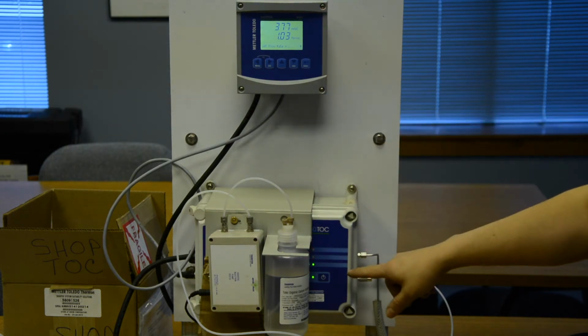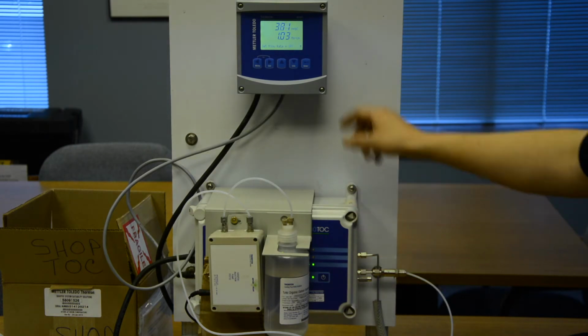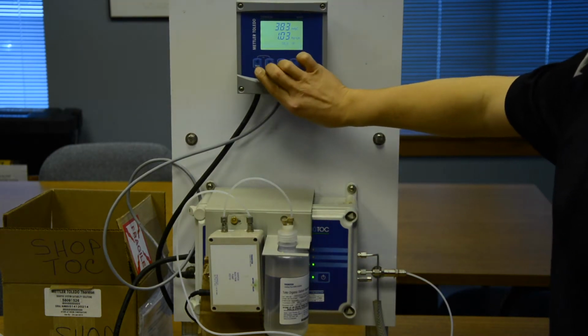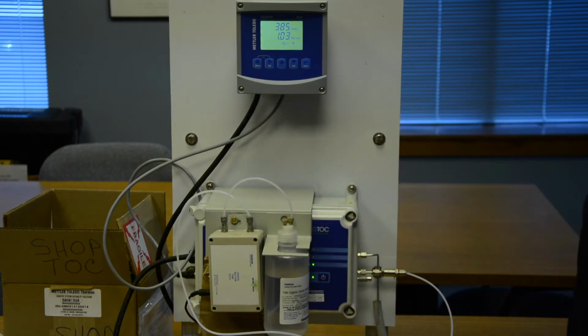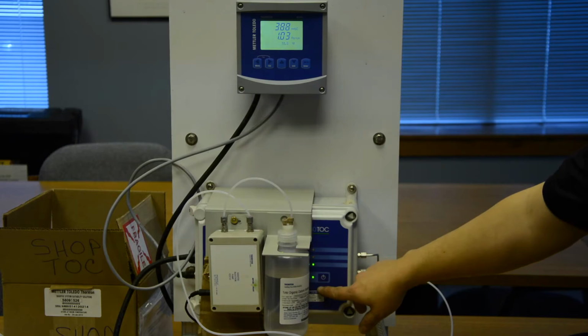At this point, you're putting your unit back into operation. Exit that menu by hitting menu and cal together, and now your unit is operating as it should. Also verify that your UV lamp is on.